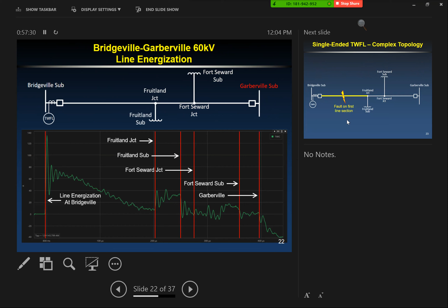So let's look at some fault events. What we would expect in looking at a single-ended fault event is for any faults on this first section, we would treat that just like a clean two-terminal transmission line - there are no taps in between. You would treat this as your local terminal, Fruitland Junction is now your remote terminal, and it's the same analysis as before. The problem is when you go out past that first junction point, that's where you start to have problems.